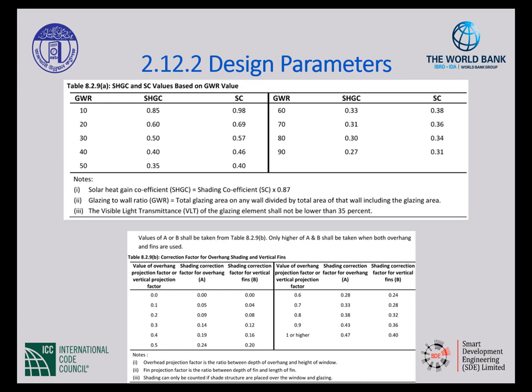And then we find these all too familiar tables on solar heat gain coefficient. So this is pretty much the exact same tables that we already looked at to say what is our window to wall area and what solar heat gain coefficient do we have to include in the design for our mechanical equipment. We did it for the building. Now let's consider that for the design of our mechanical equipment. So it gives you how to look at what's your solar heat gain coefficient based on your window to wall area, and what's your solar heat gain coefficient with those adjustment factors based on what kind of shading you did. So those exact same tables, same way of calculating, same everything got brought over here so that we make sure that we're looking at that.